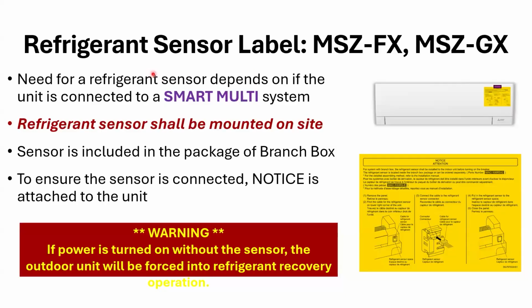Okay, let's move on. Refrigerant sensor label. So again, wall units, MSZ, FX, and the GX in particular. The need for a refrigerant sensor depends on whether the unit is connected to a smart multi system. The refrigerant sensor shall be mounted on site. Again, we're talking about smart multi right here. The sensor is included in the package of the branch box.